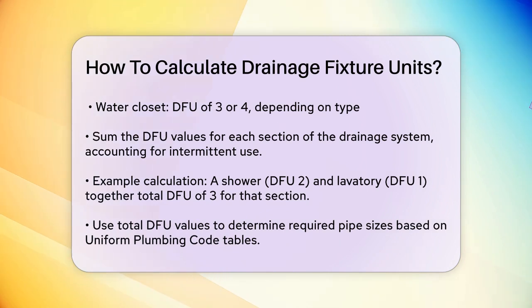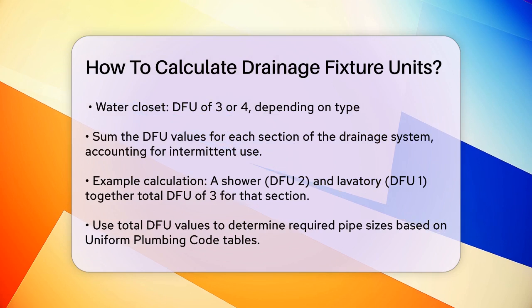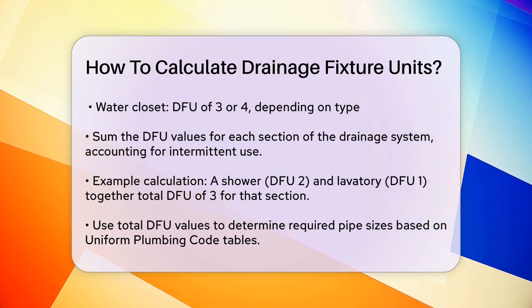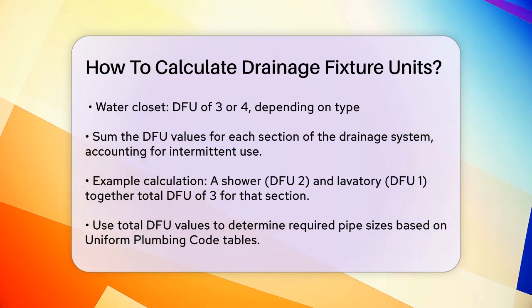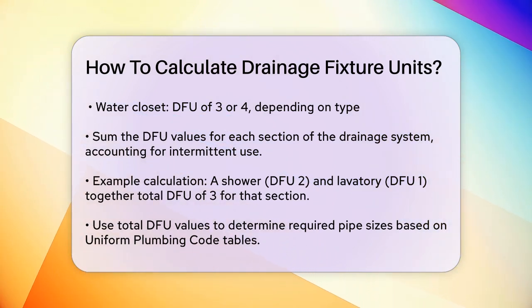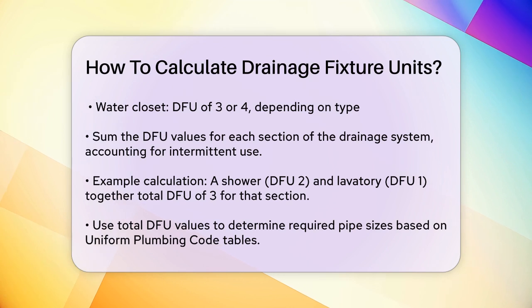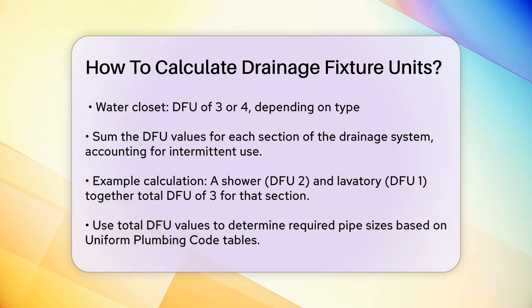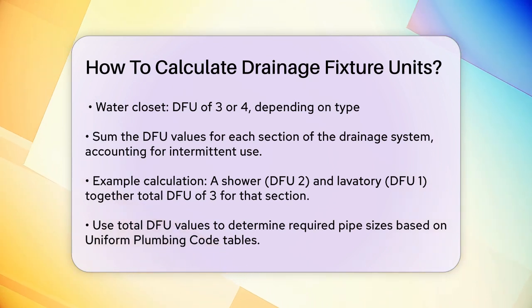Next, you use these total DFU values to determine the required pipe sizes. For example, if a pipe section has a total of 15 DFUs, you would need a three-inch pipe according to the Uniform Plumbing Code tables.